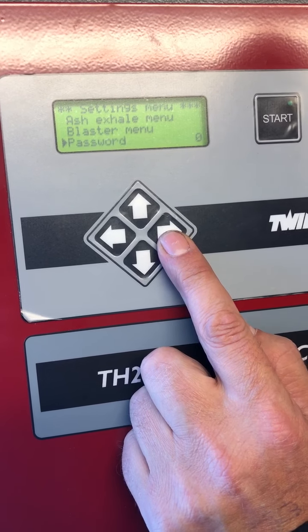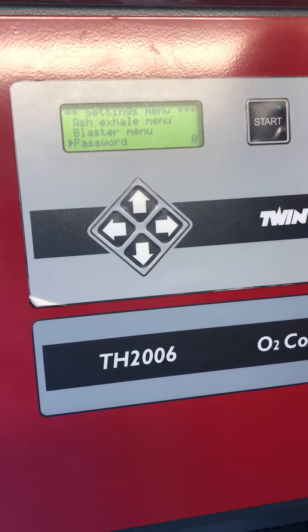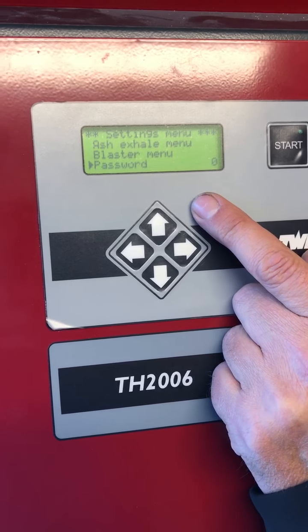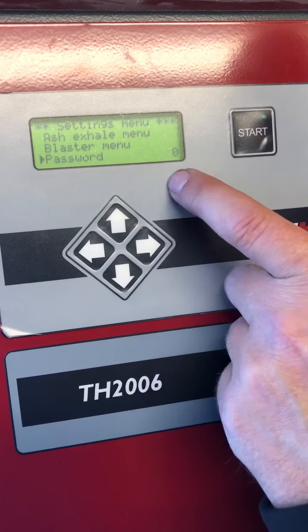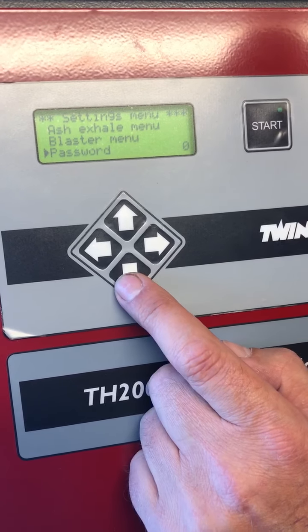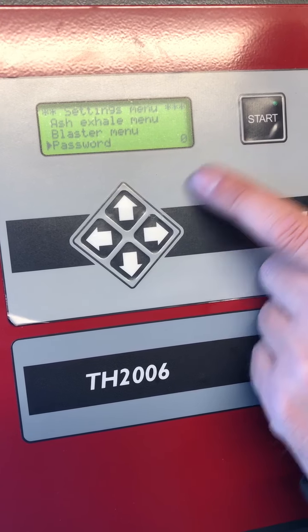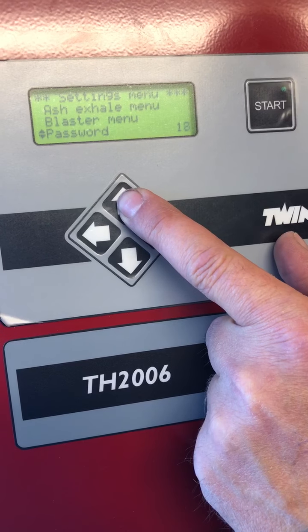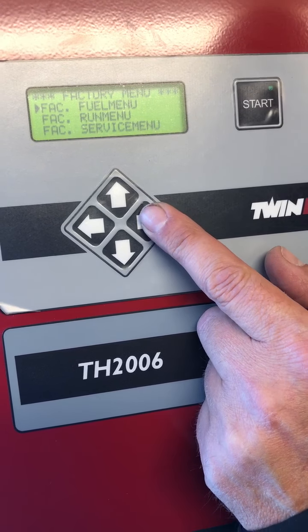Here we have passwords. If we want to go into the menu and change something — all the passwords give 10 when you add the digits. Password 37: 3 plus 7 gives 10. Password 46: 4 plus 6 gives 10. Password 82: 8 plus 2 gives 10. Remember, everything you change under the password, you have to go into password 37. Keep pressing the up/down button until you come to 37, stop, and save it with right.